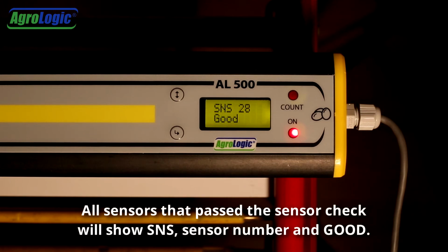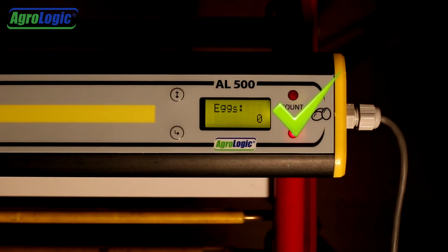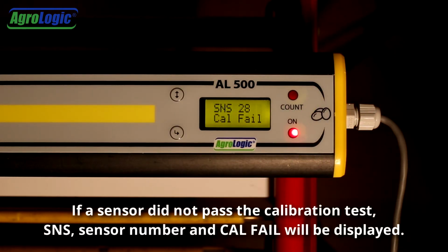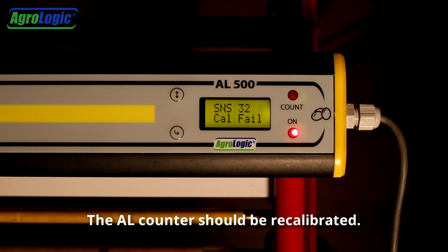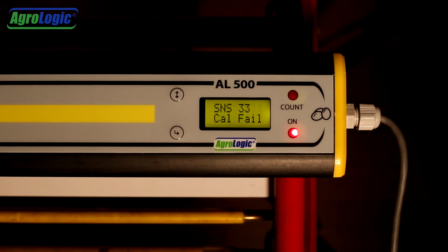All sensors that passed the sensor check will show SNS, sensor number, and good. If a sensor did not pass the calibration test, SNS, sensor number, and Cal fail will be displayed. The AL counter should be recalibrated.